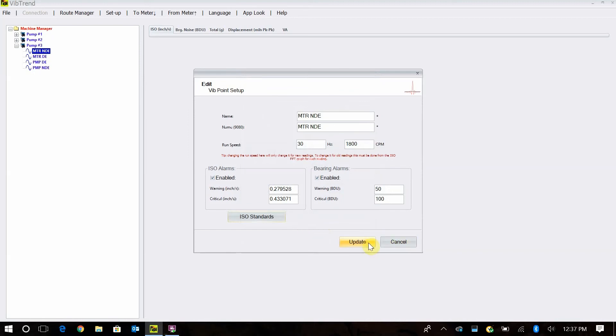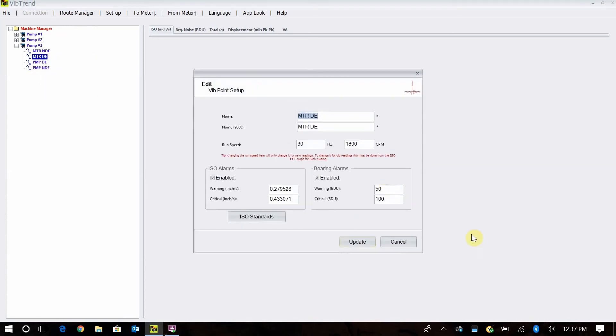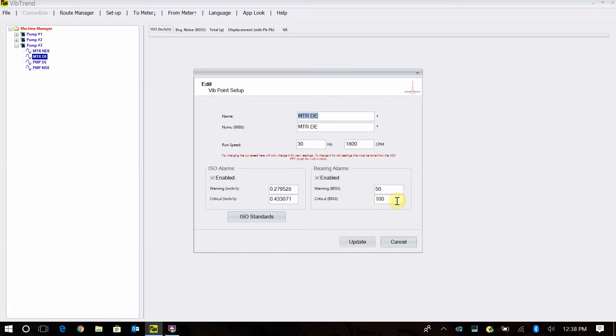Then I go cancel here after building that. The other thing you'll run into a fair amount is with your bearing damage unit alarm levels. Where we have those set at 50 and 100, we have some charts. If you edit here, everything is going to default at 50 and 100. On your pump sometimes you'll run into cavitation and different things will cause that value to go up. Speed could do it. But a good rule of thumb, most of your machines running at about 1800 should be around 50 and 100 as a good level or a good place to be. These numbers you might find you need to bump them up to 100 and 200 on an 1800. 3600 RPM, you're fairly safe to go to 250 for a caution and 350 for your critical. Just because they're turning faster, you get a lot more energy out of those alarm levels at that point.